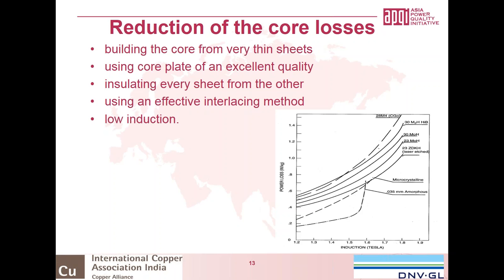And also there is a methodology to make sure that you don't have an eddy current on a large sheet. After stacking a while of sheets, make use of paper insulation between the core. Also, effective interlacing methodology, we will show the G-joints already showed, and make use of low induction within the core. That's basically what you see in the picture over there.